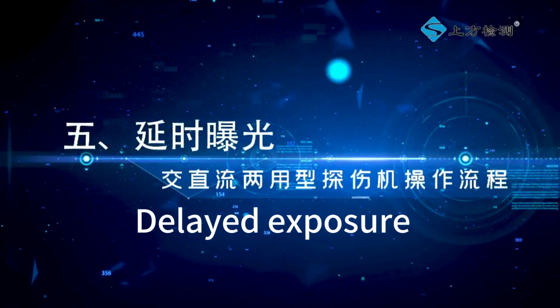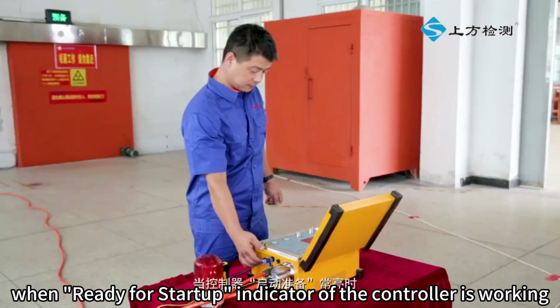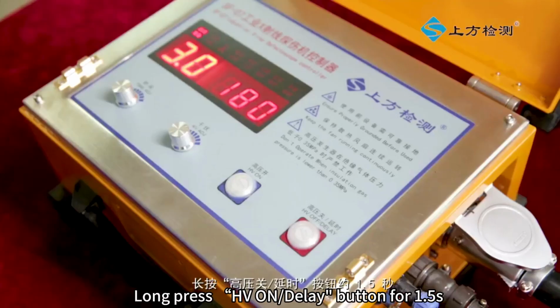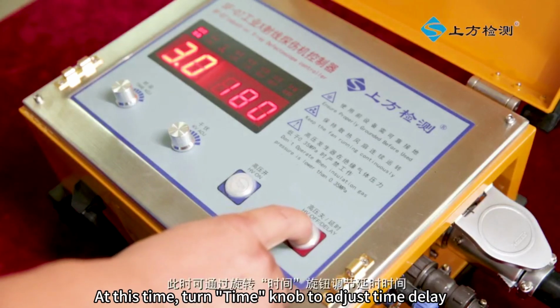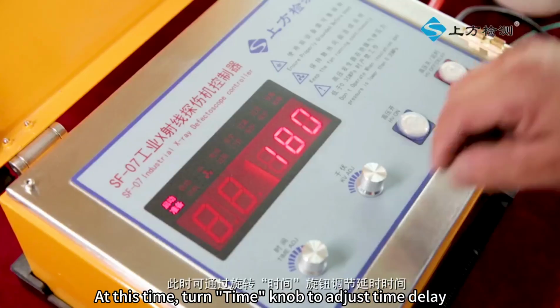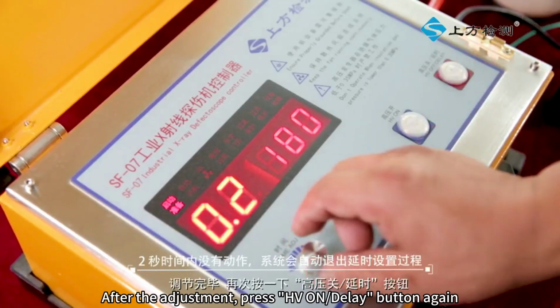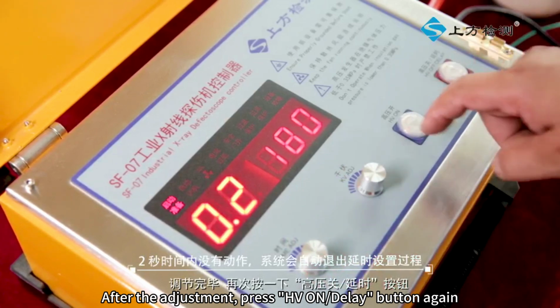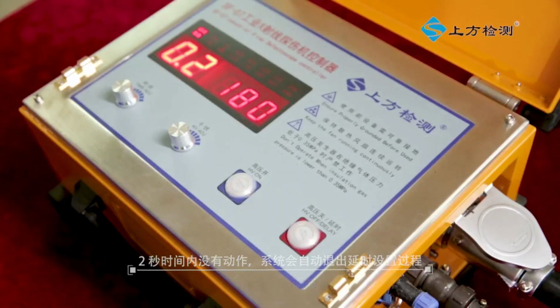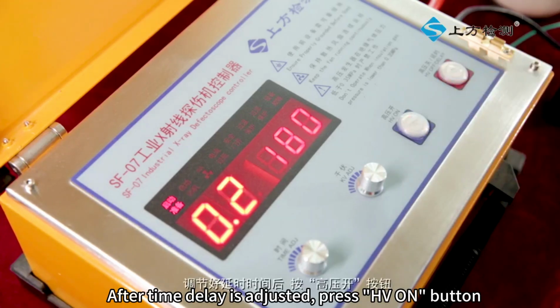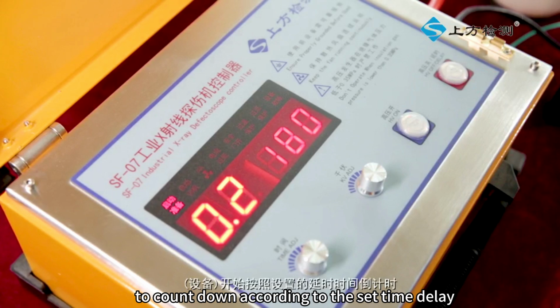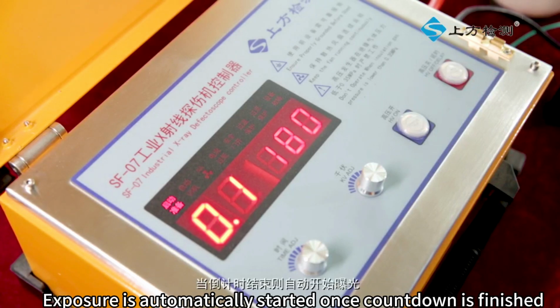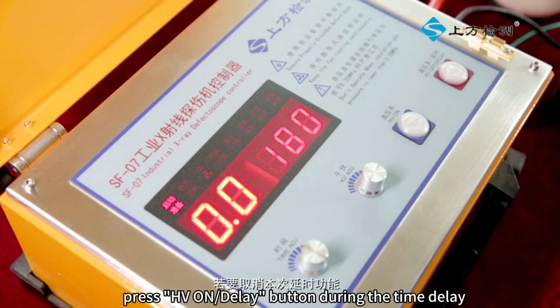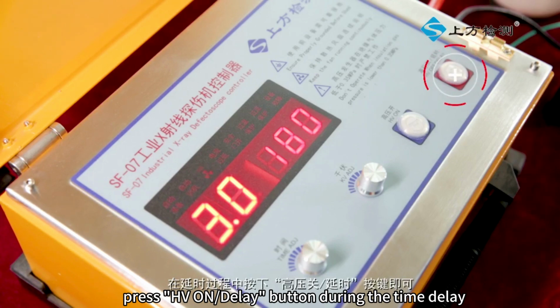5. Delayed exposure. When ready for startup and the controller indicator is working, long press the HV on/delay button for 1.5 s. Then the time display starts flashing. At this time, turn the time knob to adjust the time delay. After the adjustment, press the HV on/delay button again to quit the adjustment. After the time delay is adjusted, press the HV on button to count down according to the set time delay. Exposure is automatically started once the countdown is finished. To cancel the current time delay, press the HV on/delay button during the time delay.